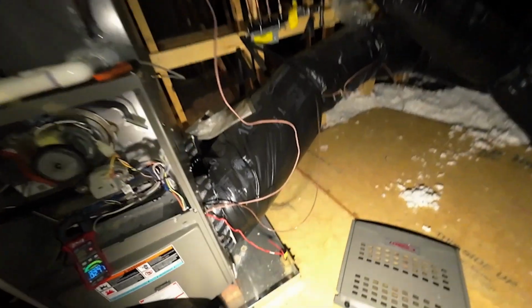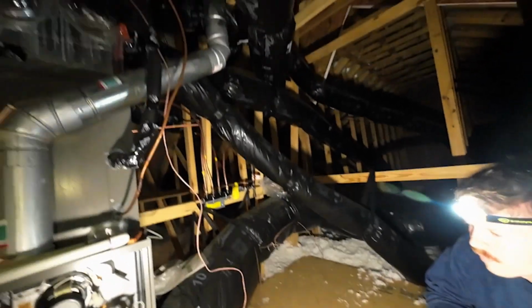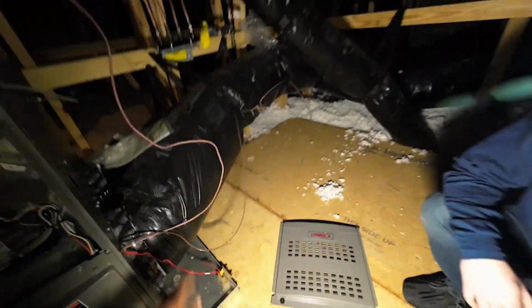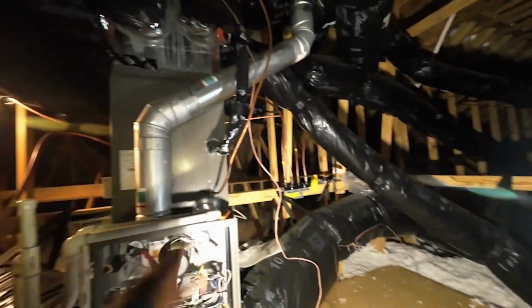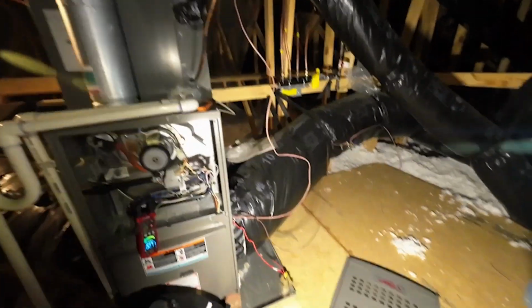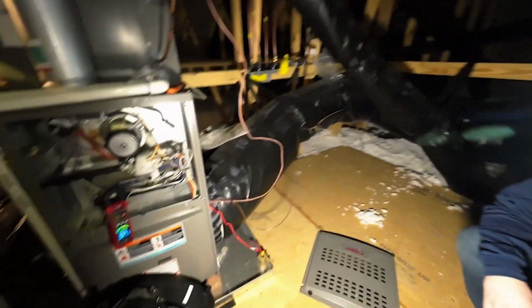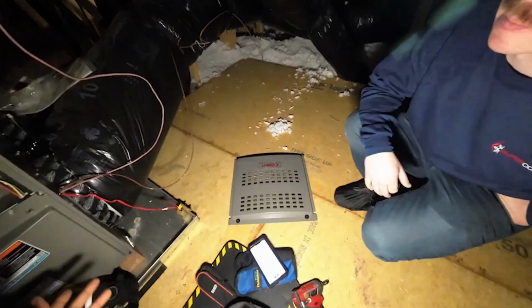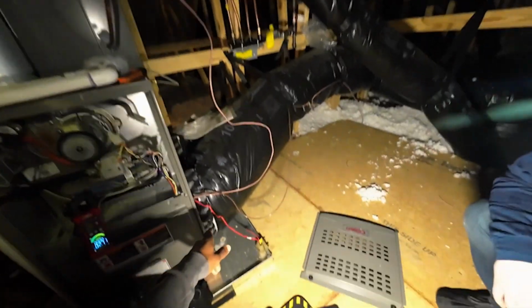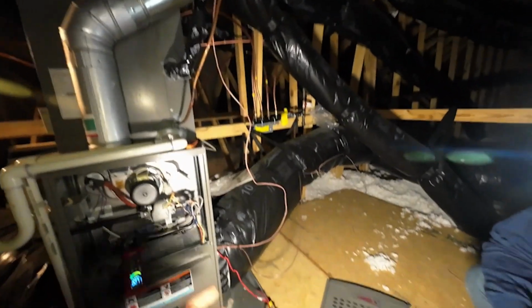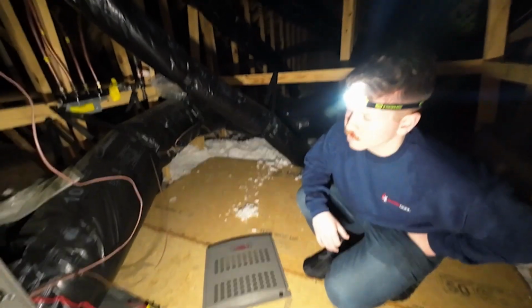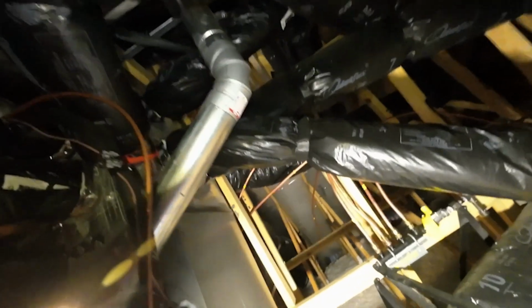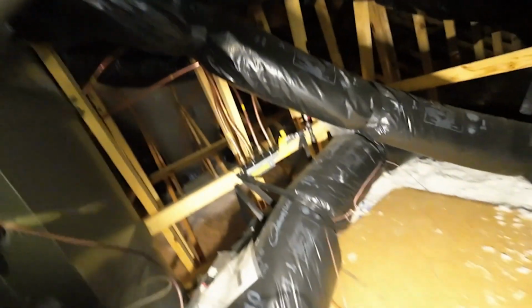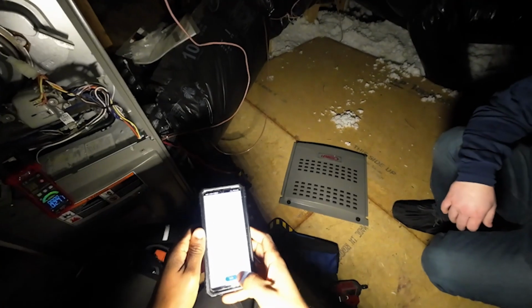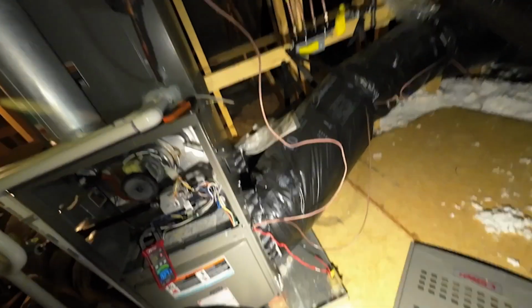Yep. So that's kind of, you know, whether people realize it or not, these are creating resistance to flow. There's ducts and, you know, everything that's put on top of this furnace or connected to the furnace is resisting the flow somehow, okay? If I take the filter out right now, you'll see that if I put the static pressure back on the return side, the static pressure will go lower because I'm taking a resistance of flow out. You got that? This only has to sit in there for maybe like, you know, 5 minutes or so. So we captured that, we apply that, 2 values captured. So that's done with that.